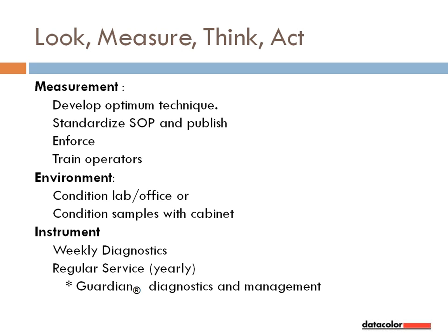For the instrument, calibrate regularly, do weekly or biweekly diagnostics, have the manufacturer's recommended service, and follow the recommended service program. Datacolor recommends yearly service. We strongly recommend Guardian Diagnostic for the Guardian product for diagnostics and fleet management.